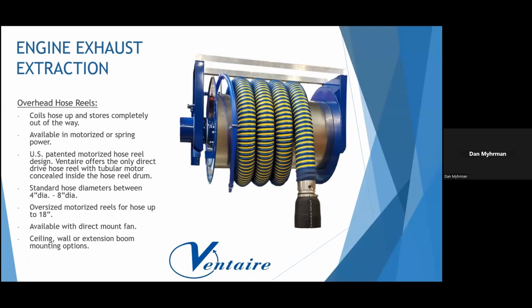Moving on to our hose reels. These are nice just because they pull the hose up completely out of the way. We offer two styles, spring and motorized. Ventaire actually has a US patent on our motorized hose reels. We're the only manufacturer to have a direct drive tubular motor. It's actually concealed inside the drum here. As far as motorized hose reels, we don't really have any limitations as far as sizing, whereas with spring we do, just because springs are only so strong to lift the hose out of the way.